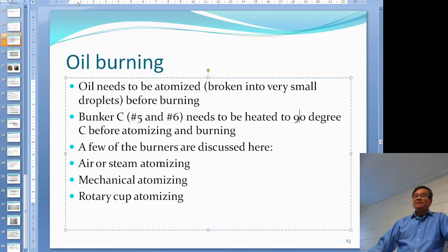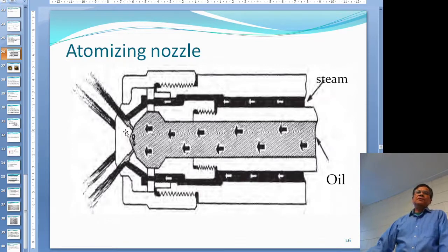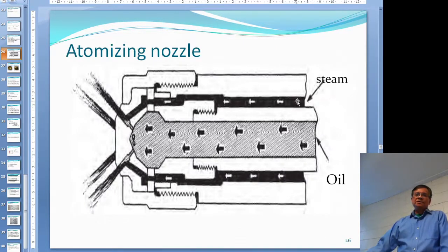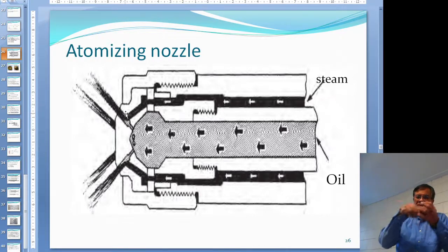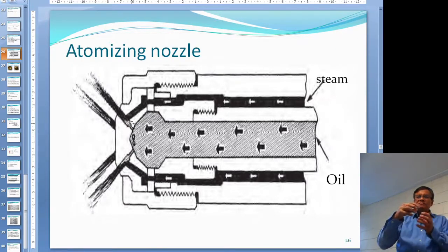For air or steam atomizing, you mix either air or steam with the oil in the center of the gun before it goes out to the furnace. The pressure of the steam or air breaks up the oil into small droplets and sprays it out. Some arrangements have the steam and oil mixture swirl as it exits, which improves mixing and burning efficiency.